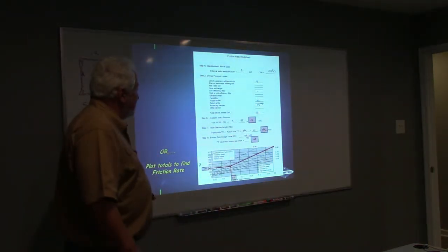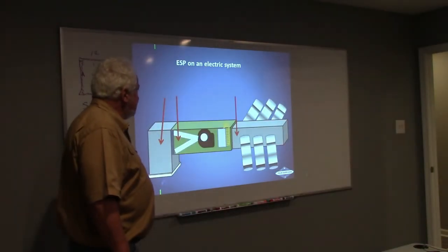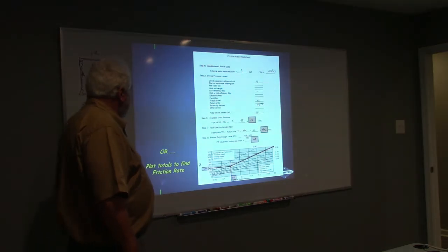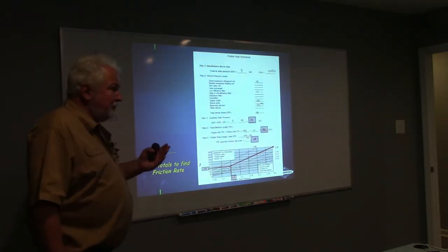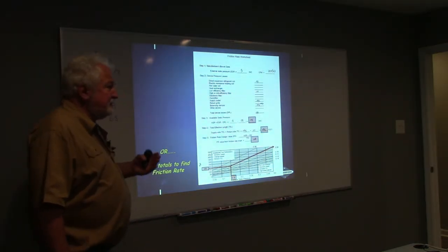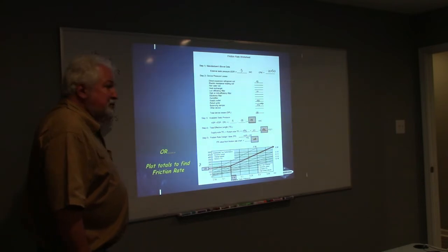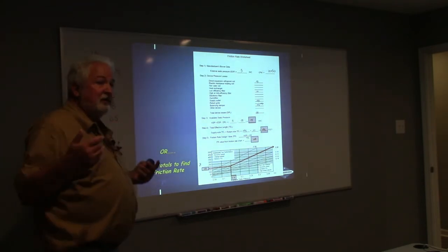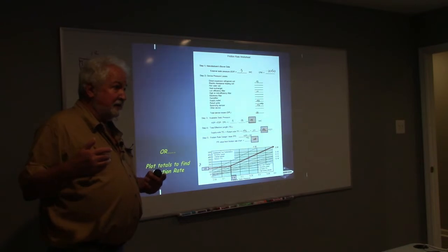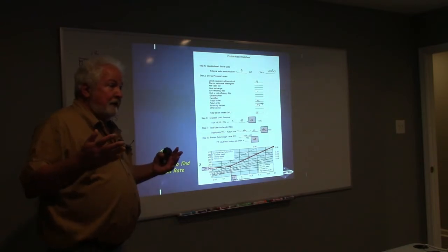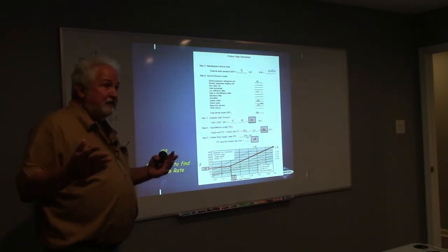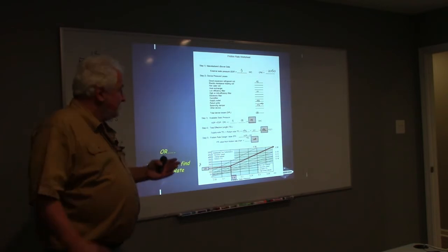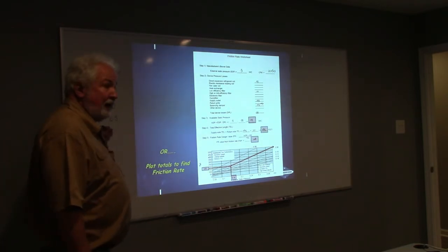Now, you can say, where did the 0.05 come from? Manual D basically says, as long as you get the supply side right, we want to slow the air down on the return side. In order to slow the air down, I have to make the ductwork bigger. So this is a SWAG. This is PADOOMA.